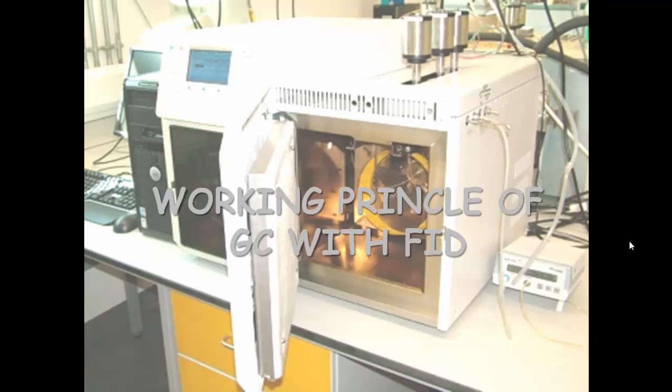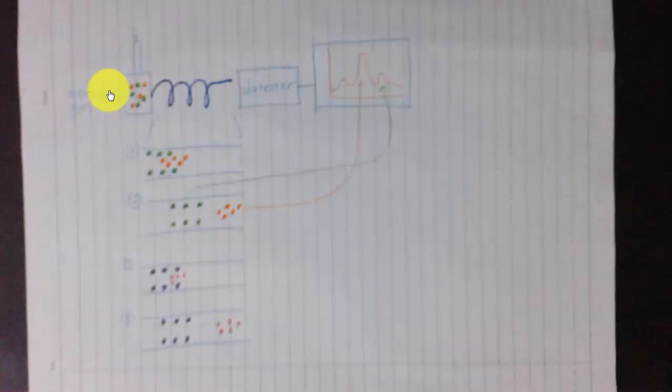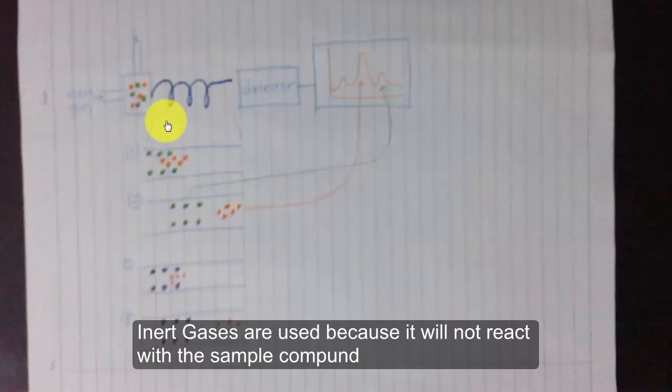I would like to explain the working principle of gas chromatography with FID using a drawing. This is where the sample compound is injected. The sample compound is evaporated into gas and stored inside the machine. For example, there are two types of compounds: the orange compound and the green compound. Inert gases are used to transport the sample compound through the column, as the sample compound cannot be transported by itself. After going through the column, it passes through the detector, which turns the reading into a readable graph called a chromatograph.